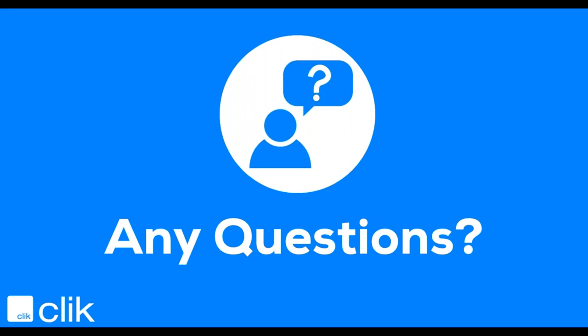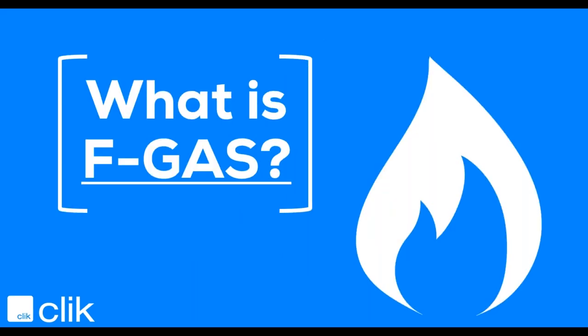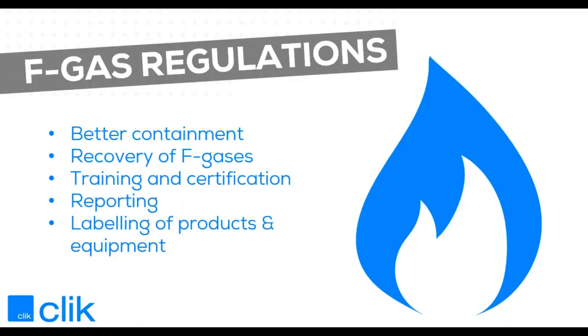So what is FGAS? The FGAS regulations were adopted in May 2006 and were later revised in 2014 by the EU. The core aims of the revised regulations included the better containment of FGASs in their applications, the recovery of FGASs from products and equipment reaching the end of their life, training and certification of technical personnel and companies working with FGAS, reporting of production, import, and export data within the EU, and labeling of certain products and equipment containing those gases.